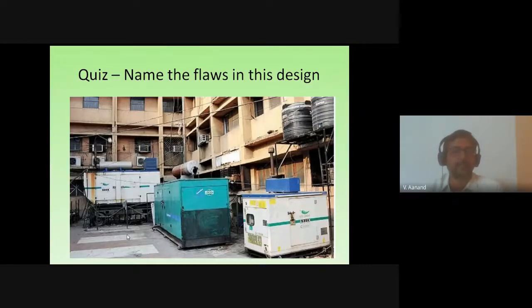To do any maintenance, I have to go through formalities, take permission from the generator operator, remove all the dangling cables, then pull the generator out. And all the more important, the generator breathes like a human being. It needs fresh air ventilation and hot air breathing out. The fresh air suction has to happen and hot air has to be thrown out. But this hot air is actually fed back into the generator, and God knows which engine or generator will malfunction or burst due to ventilation issues. All these things have to be taken care of. This isn't pertaining to interior designing, but there are offices with separate generator requirements even for interior installations.